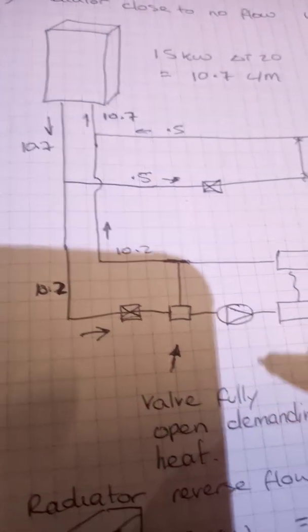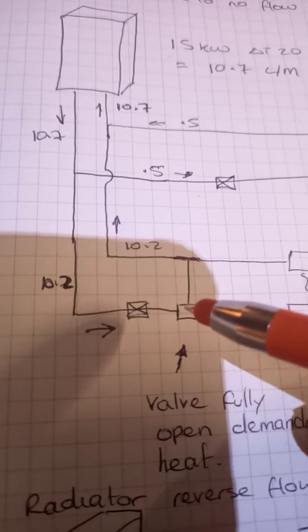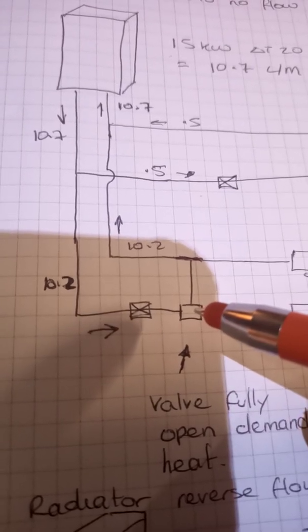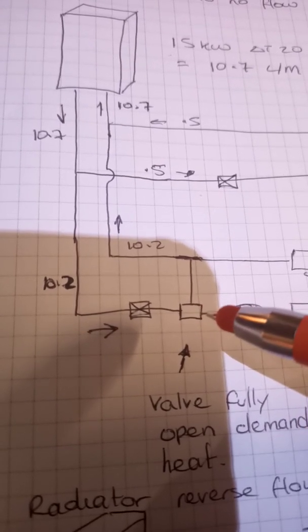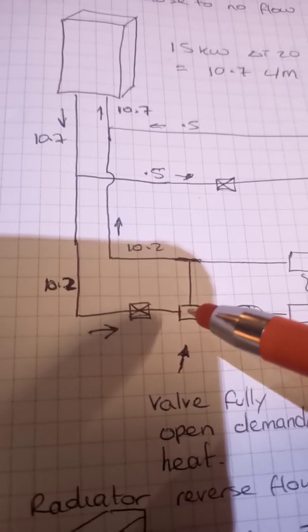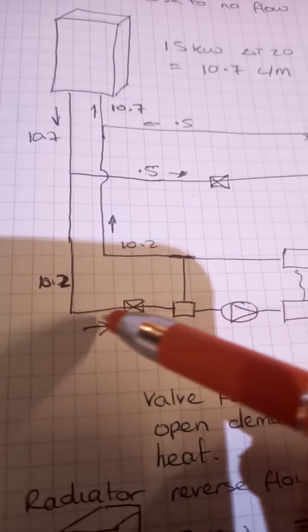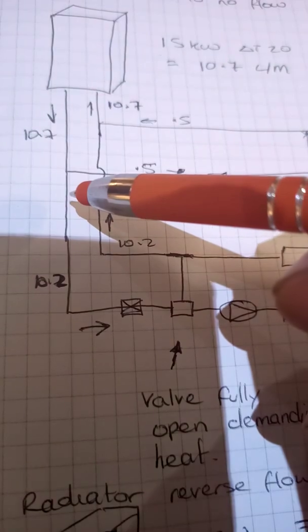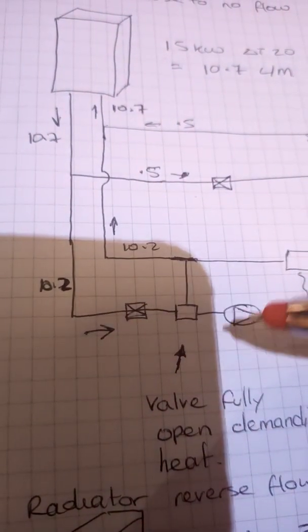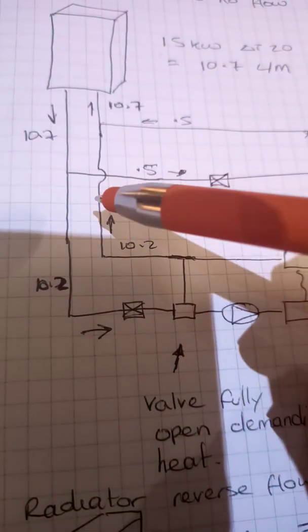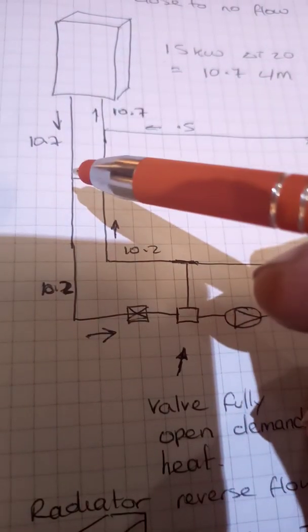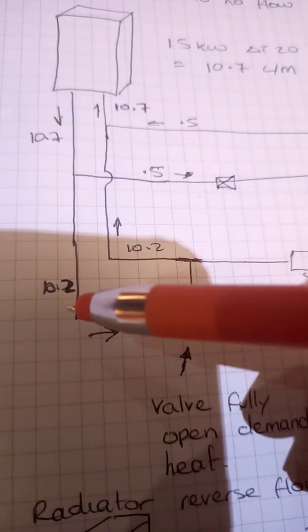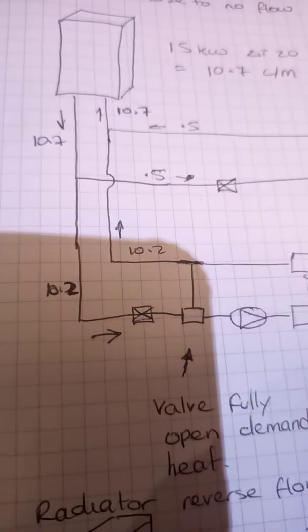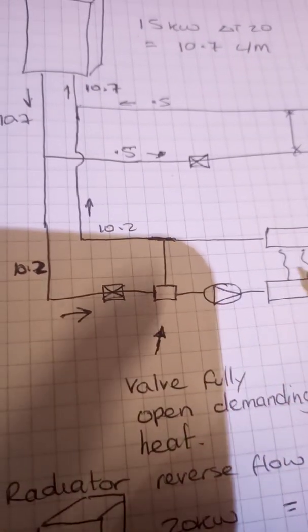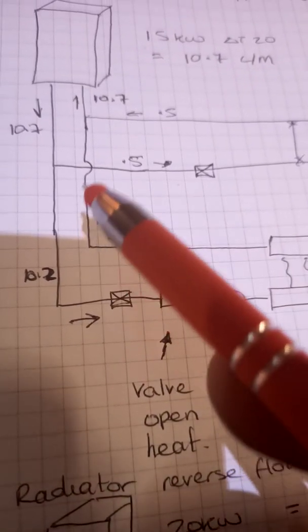Well, our underfloor heating has a pump here. The valve will be fully open in this scenario. I'll explain about that in a bit. The valve will be fully open. So this pump will be providing a nice negative pressure on this side, which will be meeting the flow from the boiler. So we're going to get a draw here of the required flow rate, 10.2, which is going to go around the floor manifold and come back.